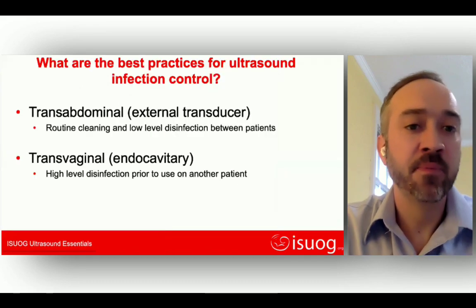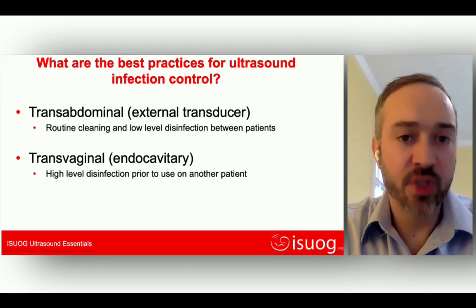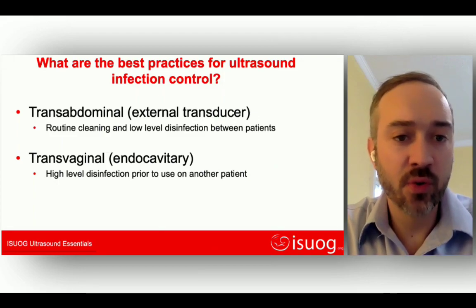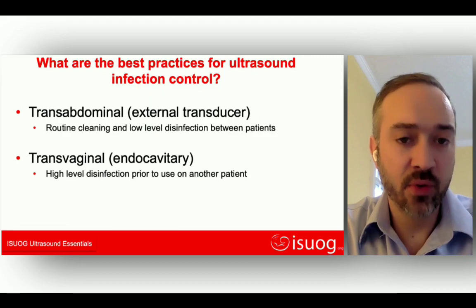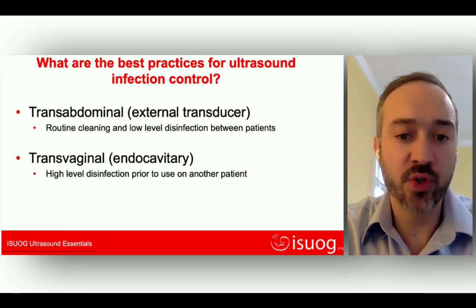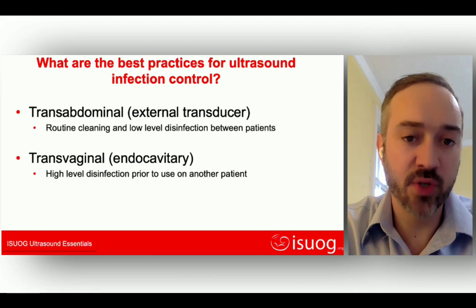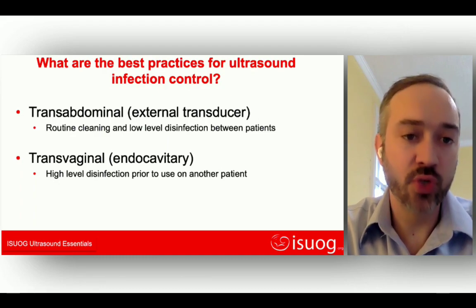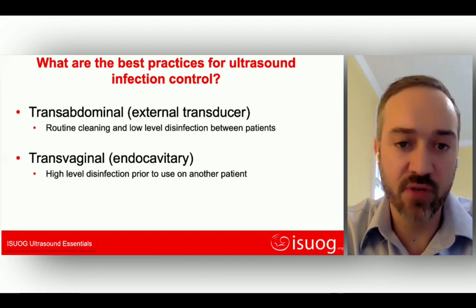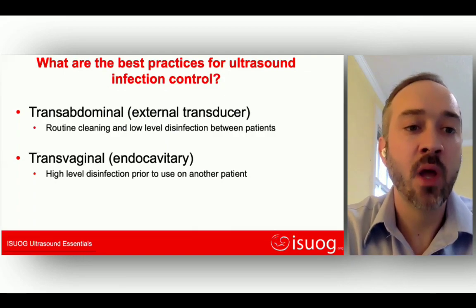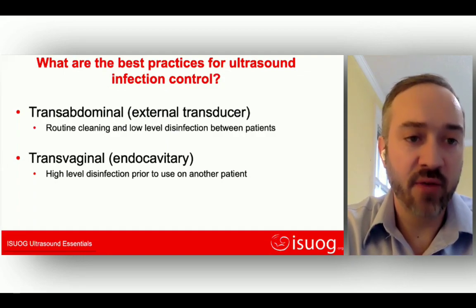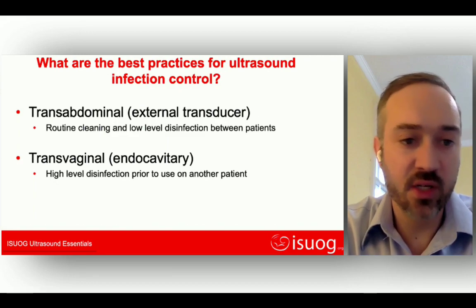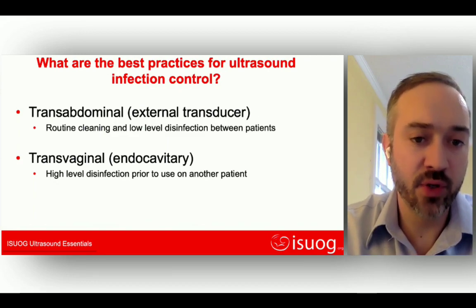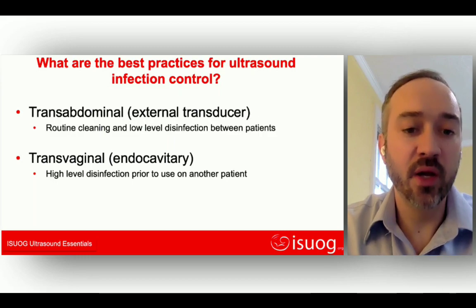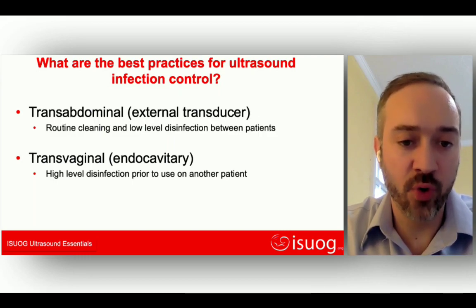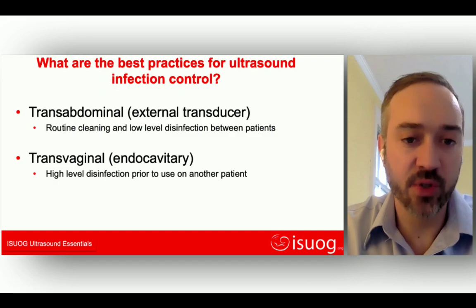So on to our topic. We're going to go over the best practices for ultrasound infection control. Transabdominal or external transducers, like you use for the standard second and third trimester obstetric scan, need routine cleaning and low-level disinfection between patients. A transvaginal or endocavitary probe needs high-level disinfection prior to use on another patient. Again, the key risk to avoid would be transmission of human papillomavirus, HPV.